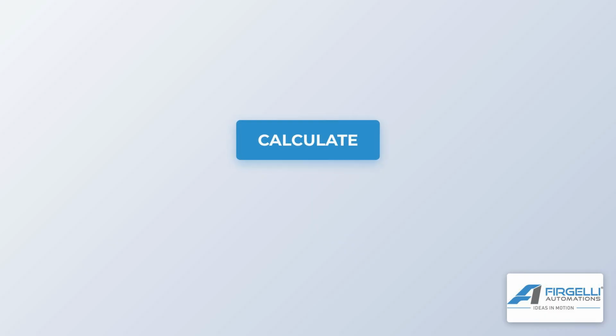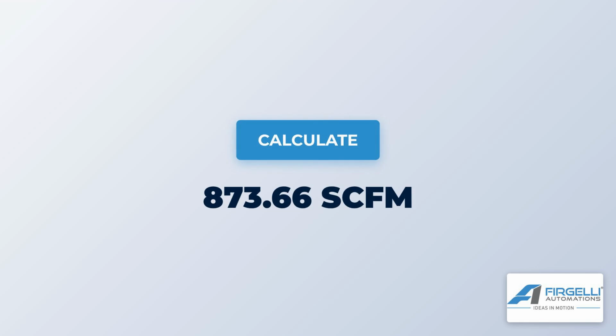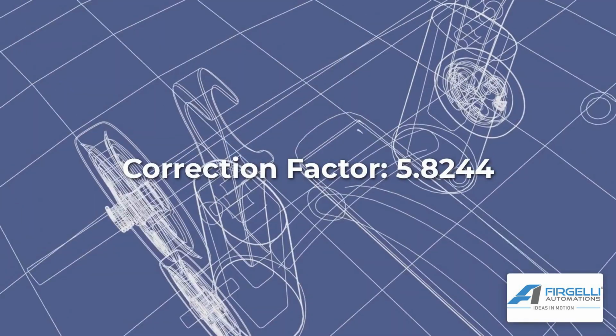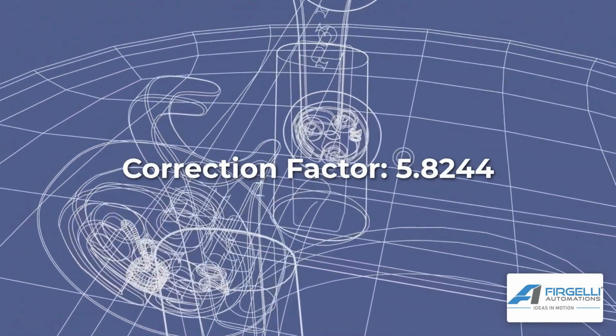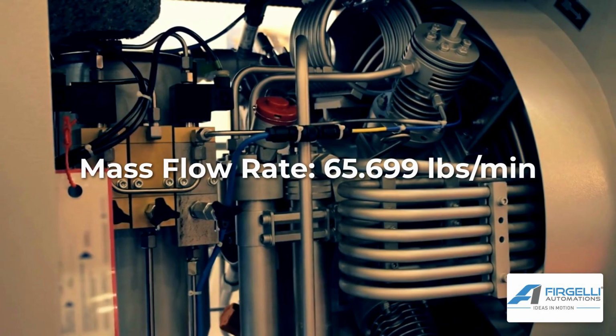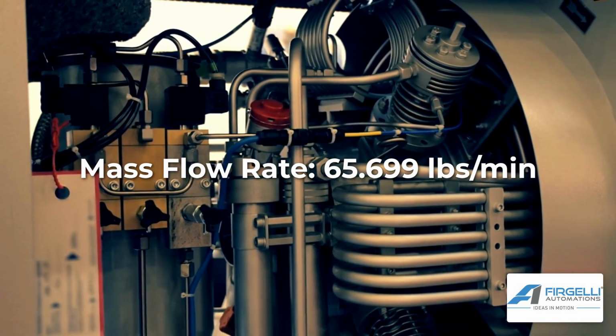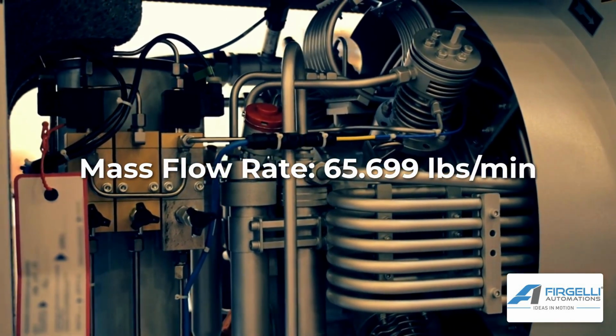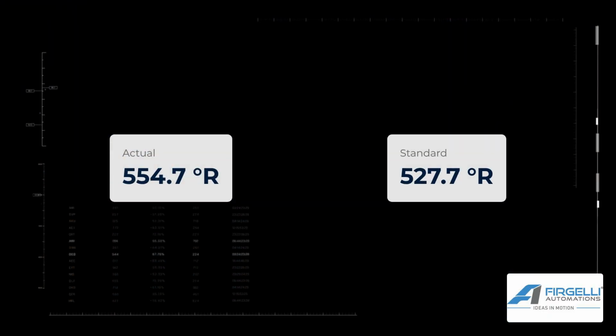After clicking Calculate, we get our primary result of 873.66 SCFM. The secondary result shows a correction factor of 5.8244. Additional outputs include the mass flow rate at 65.699 pounds per minute for air, plus the converted temperatures, 554.7 degrees Rankine actual and 527.7 degrees Rankine standard.